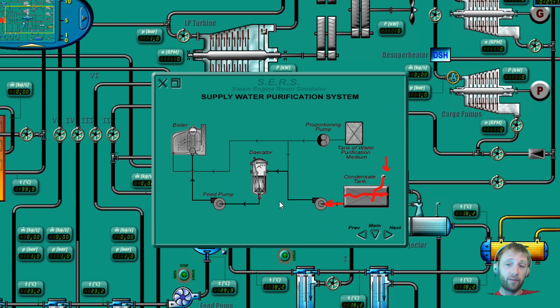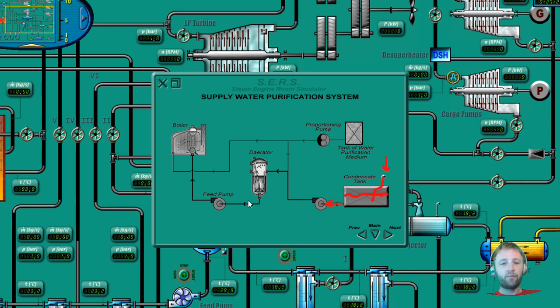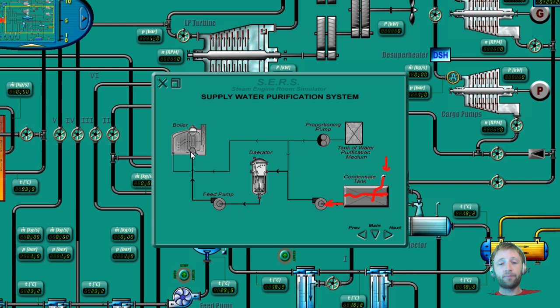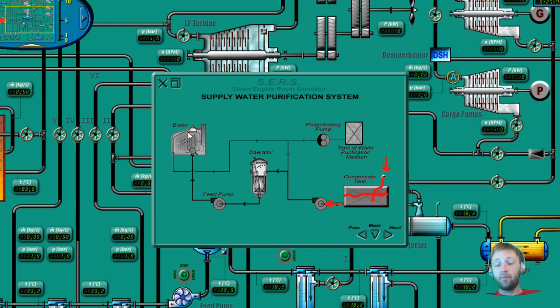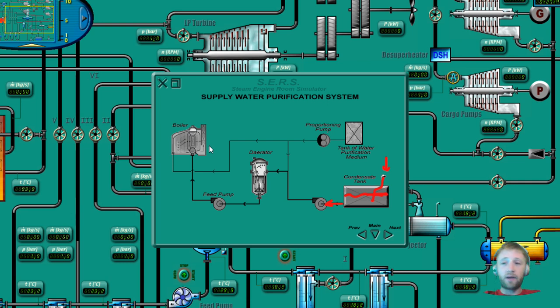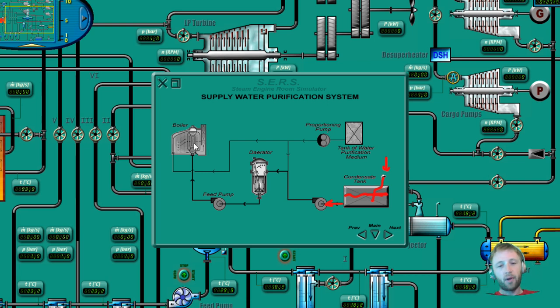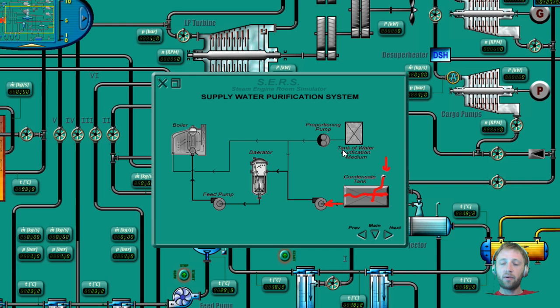The oxygen itself is really a fuel, a really fast burning thing that can make damage to everything that contacts it. And it's extremely flammable when the concentration is above some limits. So after the deaerator, we have our feed pump. Our water, we already deaerated it, and we can send to our boiler. As you can see, the water enters here on the bottom, and then it will be heated up and slowly by the natural circulation here will be sent here to the steam drum on the top.